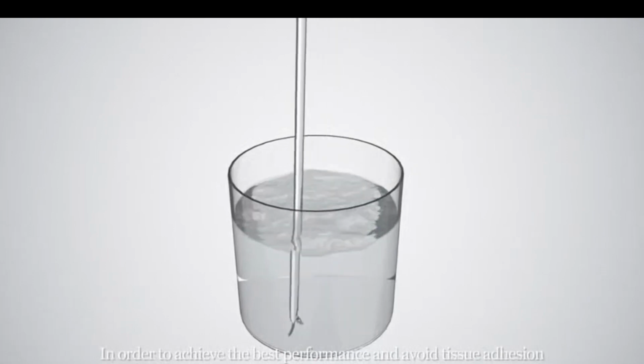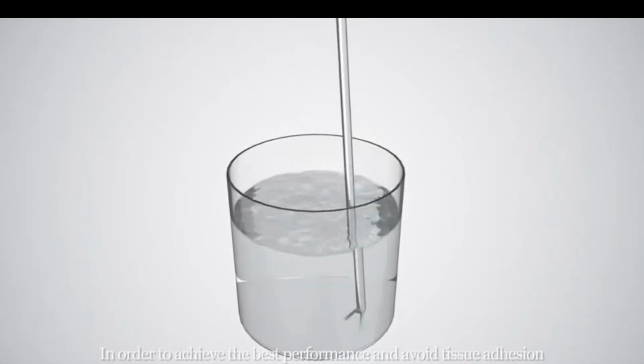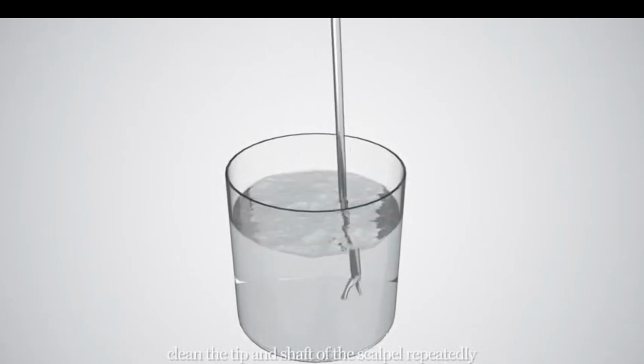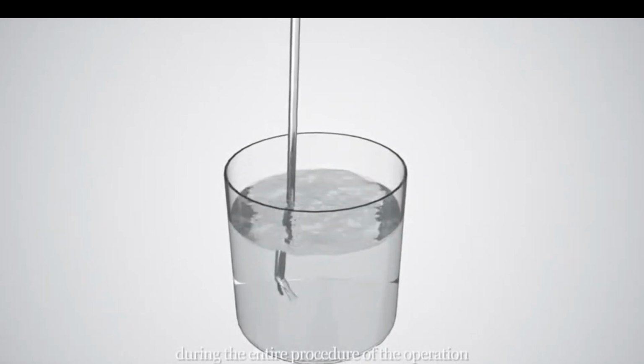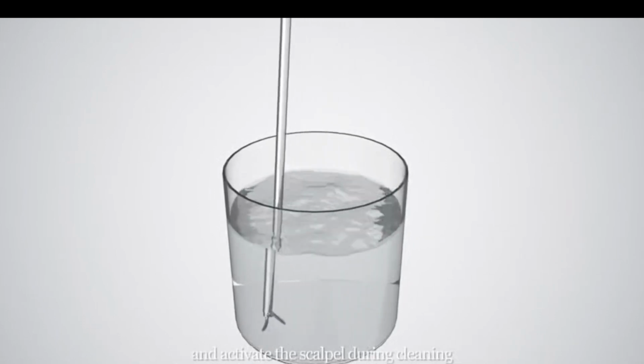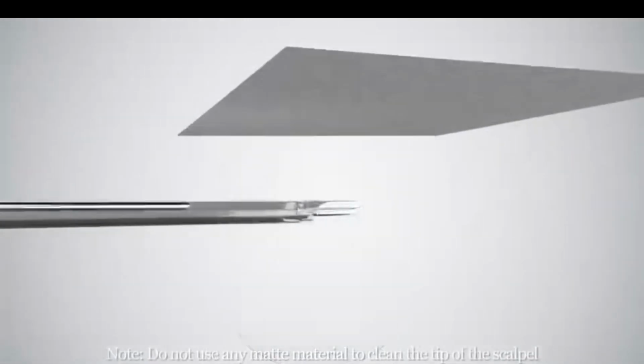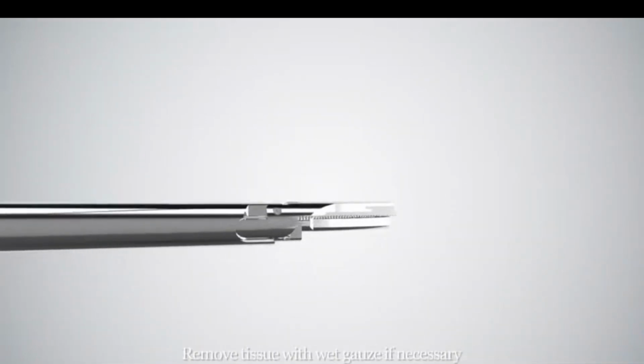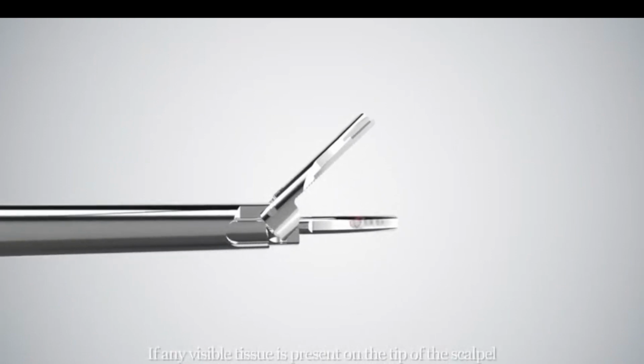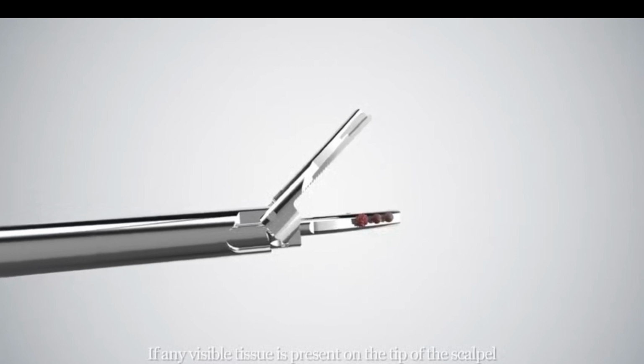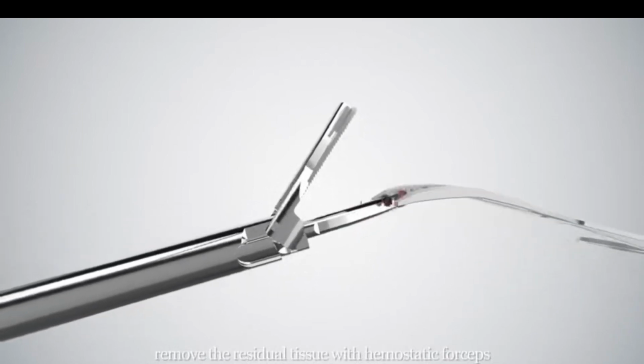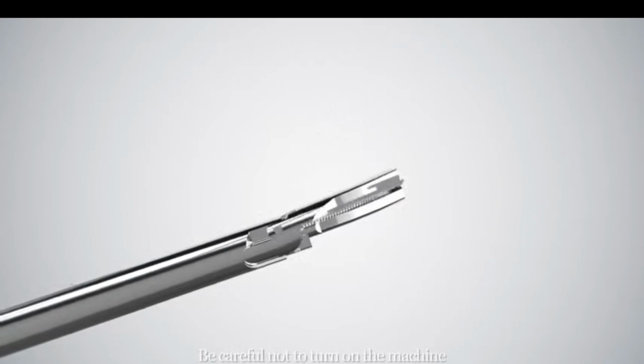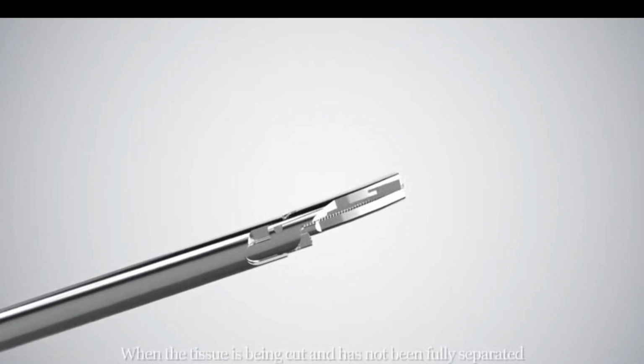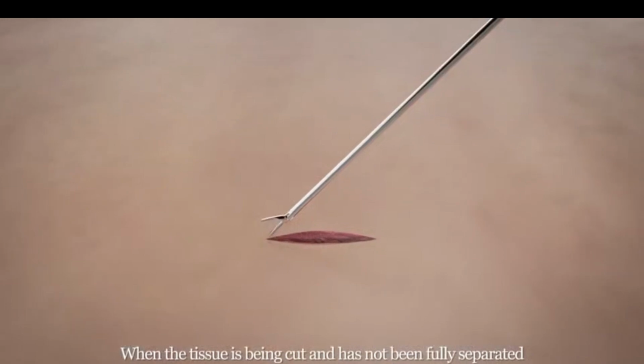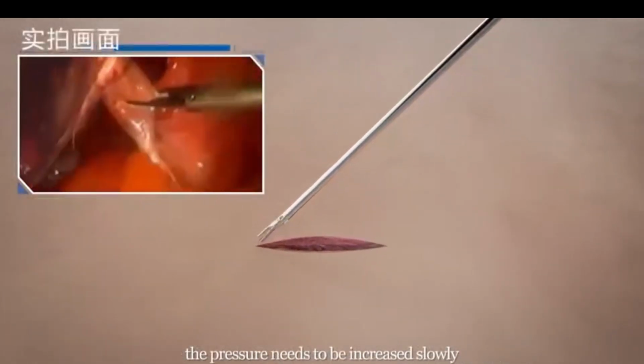In order to achieve the best performance and avoid tissue adhesion, clean the tip and shaft of the scalpel repeatedly during the entire procedure of the operation, and activate the scalpel during cleaning. Note: do not use any matte material to clean the tip of the scalpel. Remove tissue with wet gauze if necessary. If any visible tissue is present on the tip of the scalpel, remove the residual tissue with hemostatic forceps. Be careful not to turn on the machine. When the tissue is being cut and has not been fully separated, the pressure needs to be increased slowly.